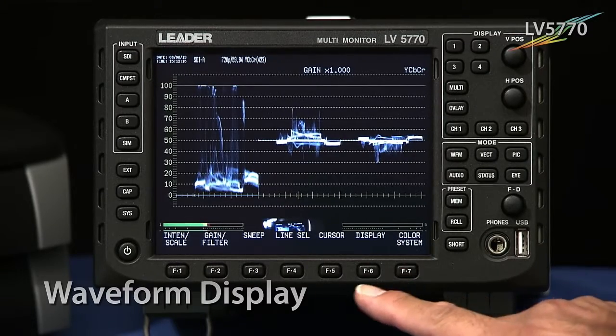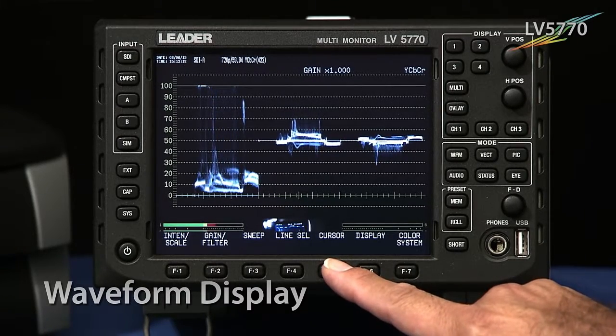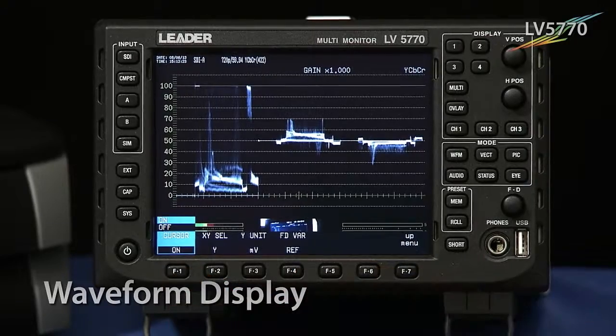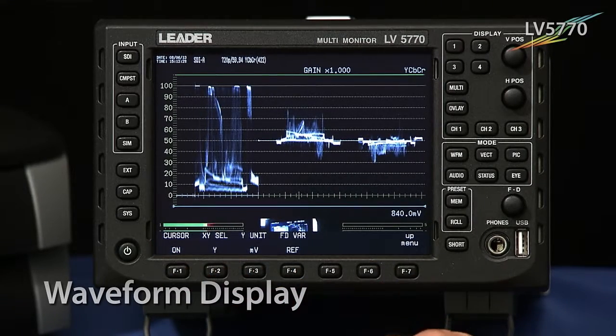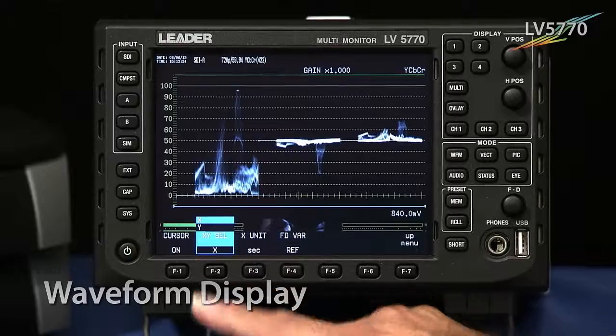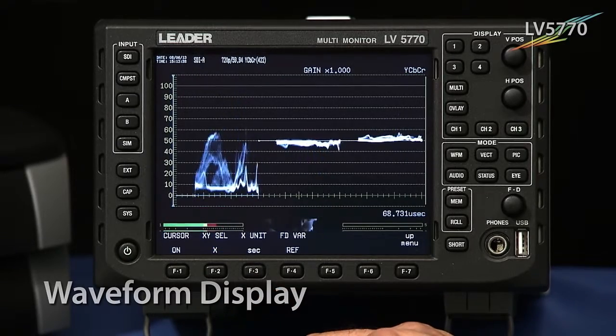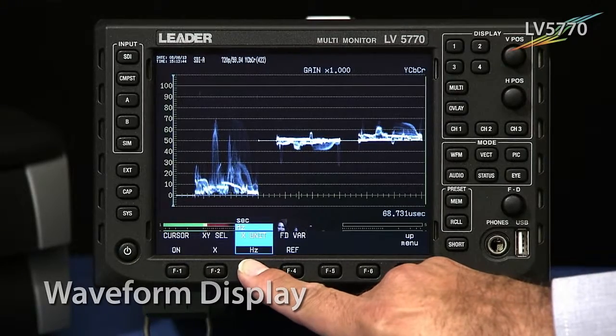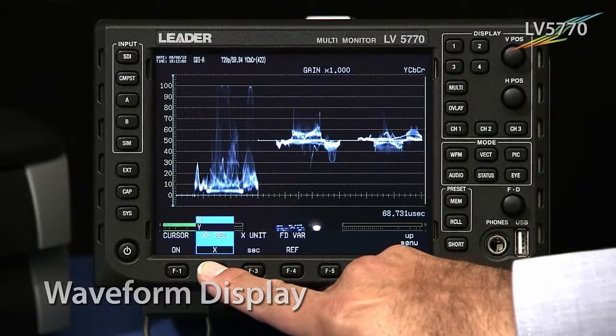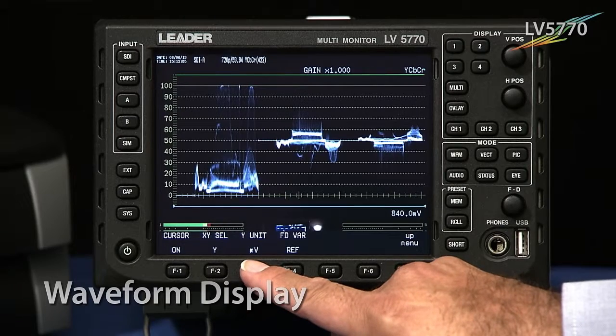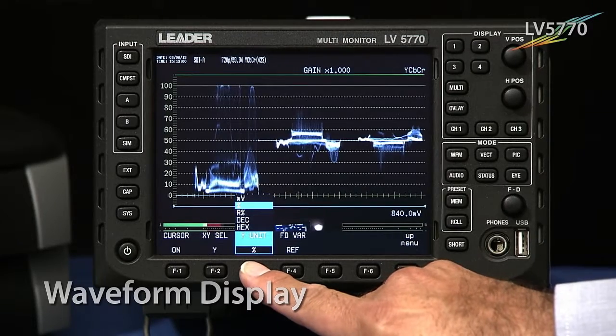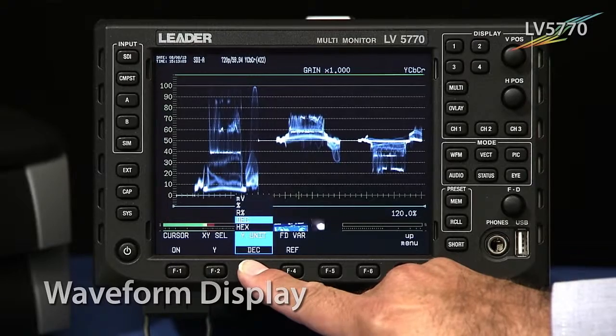We'll turn that back off, go back up the menu, and move to the next item, which is F5 — the cursor display. Hitting that brings us down into the cursor menu, and we'll turn on the cursors. This allows you to do measurements based on the Y-axis for amplitude and also the X-axis for timing measurements. Going over to F3 when you're doing timing allows you to select cycles or seconds as the unit of measurement. Moving to the Y-axis allows you to do measurements in terms of amplitude, which with F3 can be either in millivolts, percentage, or digital values.